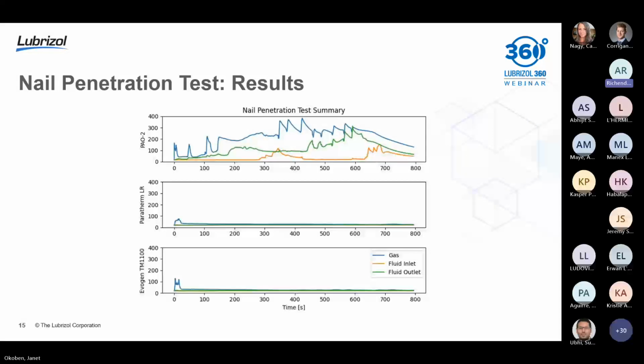In this graph, you're looking at 3 separate fluids in the top, middle, and bottom, and in each graph you see 3 curves: the gas curve, the fluid inlet, and the fluid outlet. The gas is a thermocouple located just above the module, just above one of those burst discs. As the gas develops and releases from one of the cells going into thermal runaway, it'll be captured by this thermocouple.